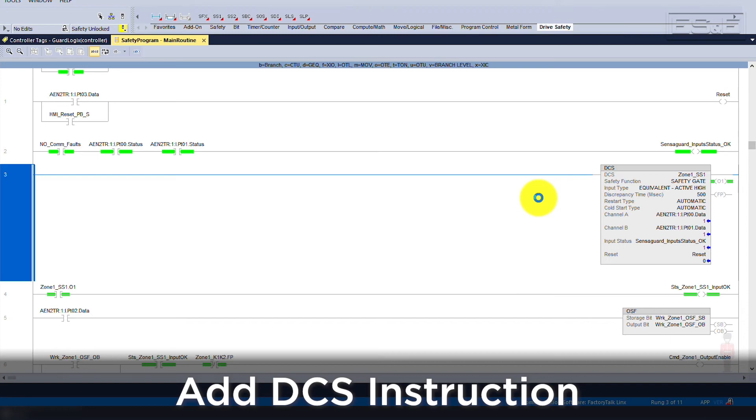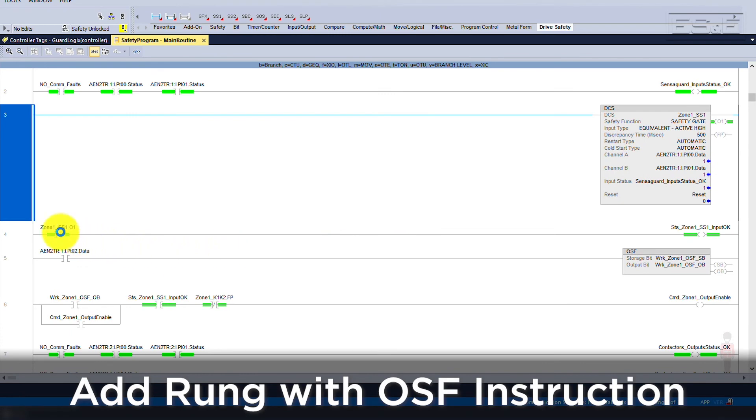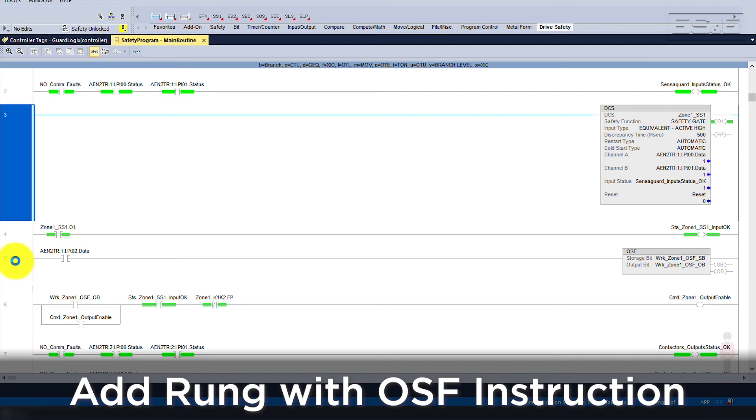After the DCS is set up, we will need to create another rung using a one-shot falling or OSF instruction. This is the safety reset input. Many people use the same reset command for both fault reset and safety reset, but the safety reset is needed along with the OSF instruction to maintain our performance level D requirements. Original code didn't require the OSF, but it was proven necessary and is easily overlooked, so ensure that you have that instruction.